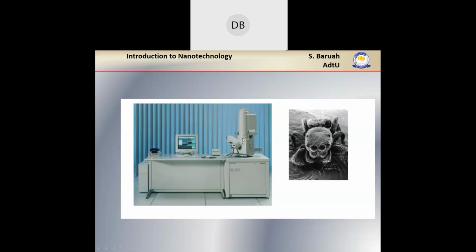So this type of SEM, because of this compromise we are making on the electron beam, that means this variation in pressure, these types of electron microscopes cannot go to very high magnifications. All right. So this type of microscope can go to a maximum of about 10,000 times magnification. Whereas the other SEM, where we have the same pressure inside the whole column, can go to about 1 to 2 million times. 10,000 times, sorry, versus million times. You see the difference, all right? But we have no choice.